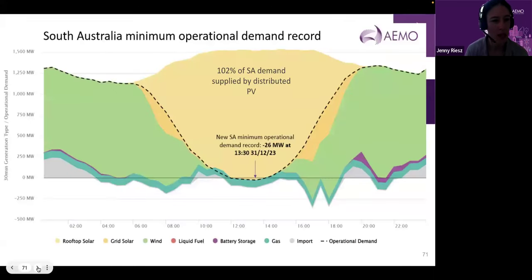This shows the levels of distributed photovoltaics we've reached in South Australia. Just recently, on New Year's Eve, December 31st, we hit a new record where total net demand in South Australia was negative 26 megawatts — meaning 102% of demand was supplied by distributed photovoltaics, essentially rooftop solar, from systems as small as 5 kilowatts. That means it was backfeeding from the distribution network to supply industrial loads, including large mines and other industrial customers, totaling about 1.2 gigawatts of demand supplied by those rooftops. It was a historic record and we've learned a lot from studying that day.